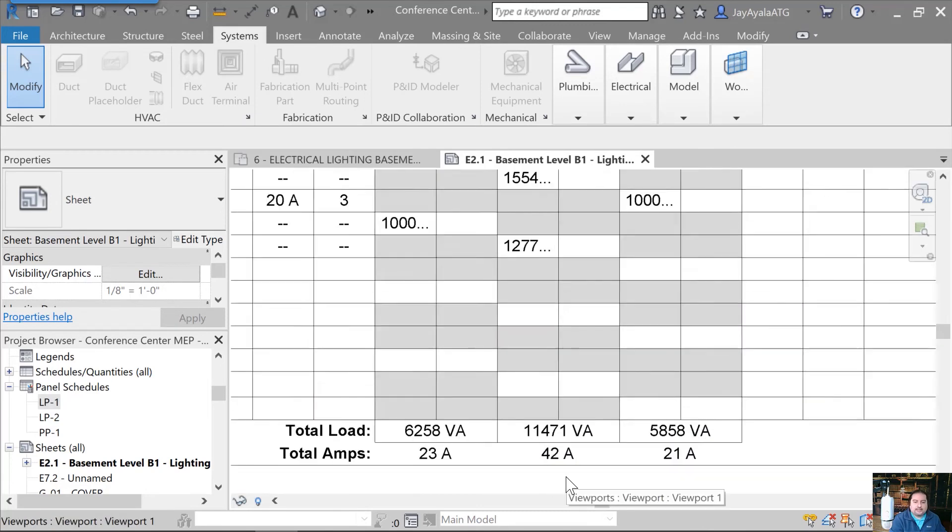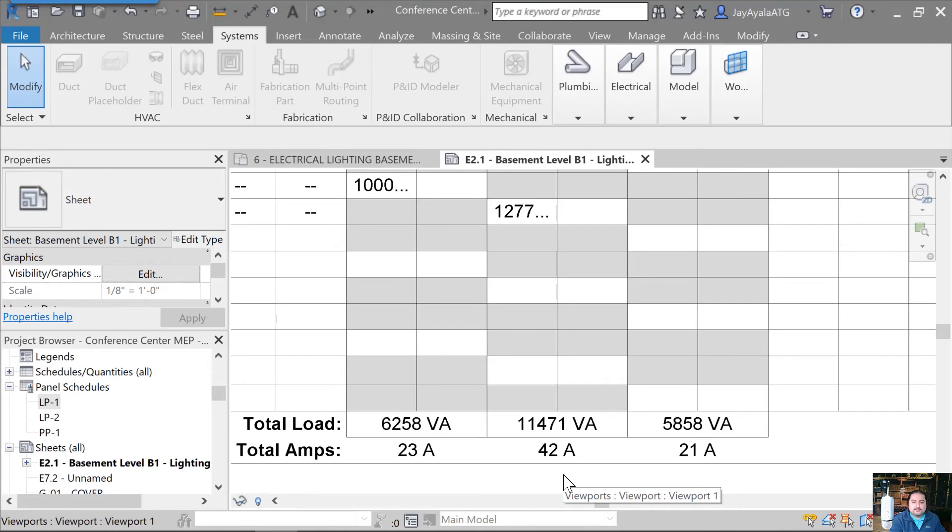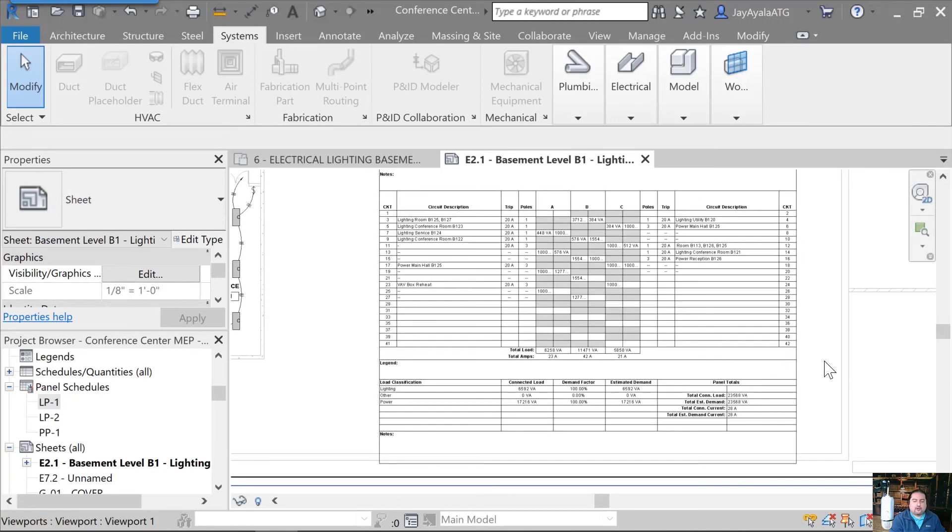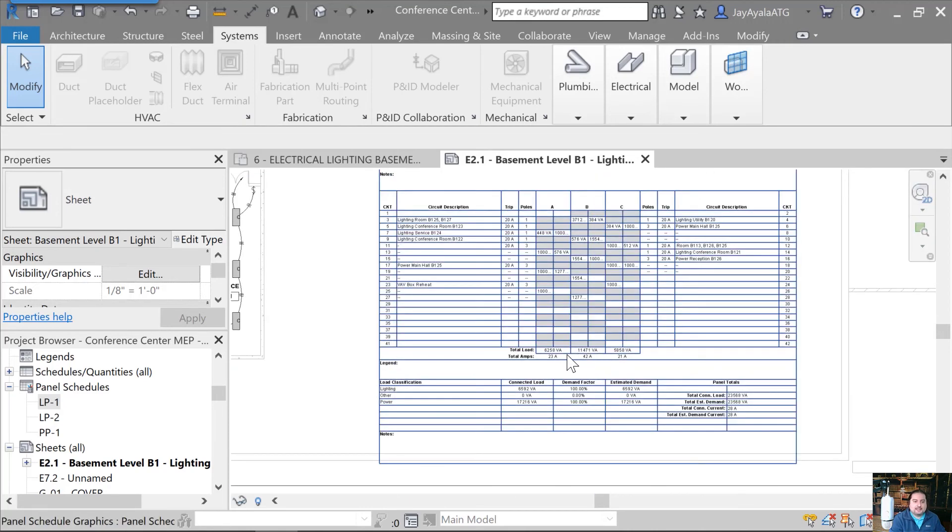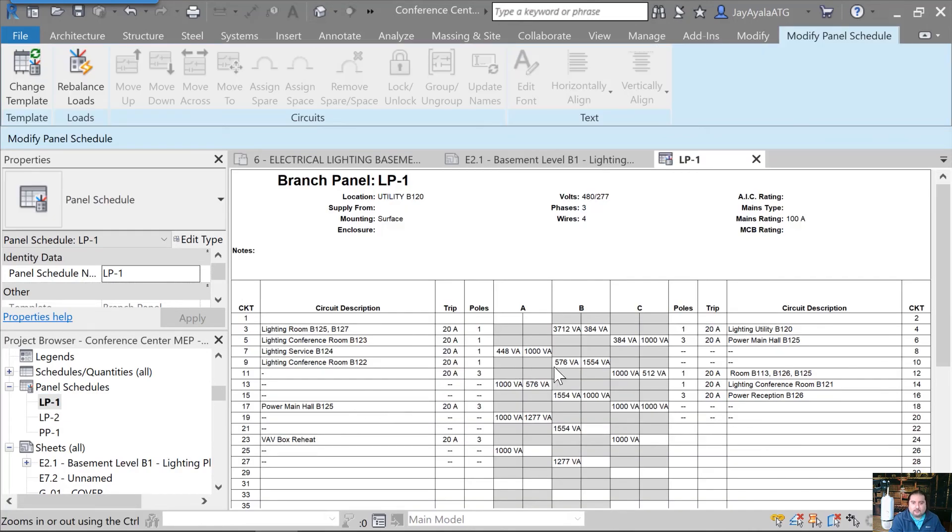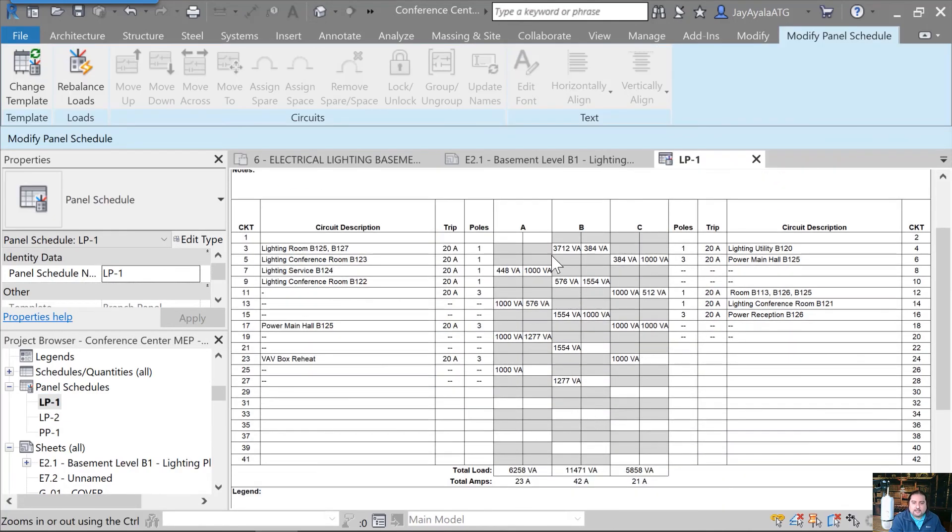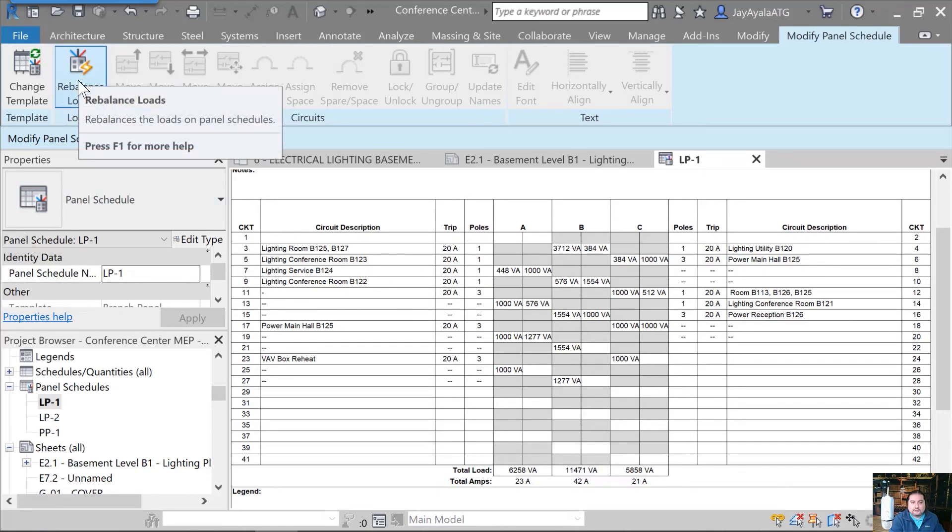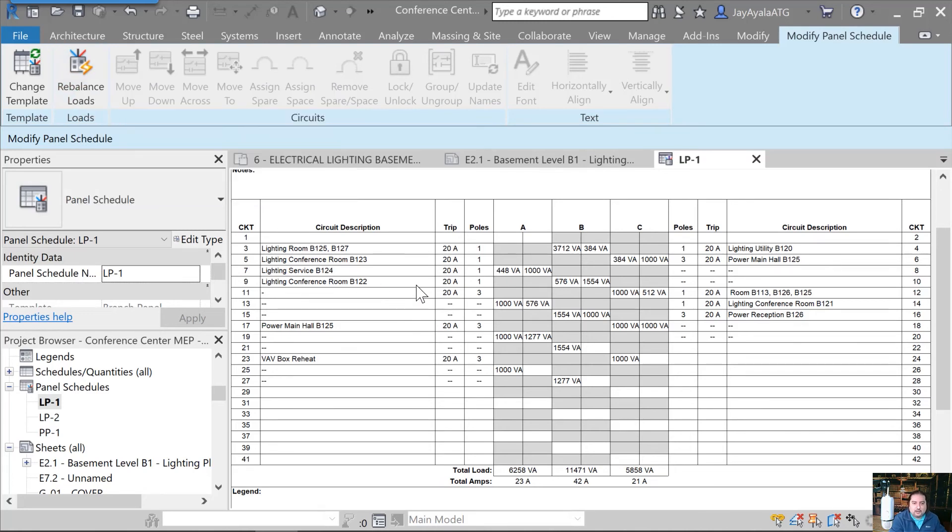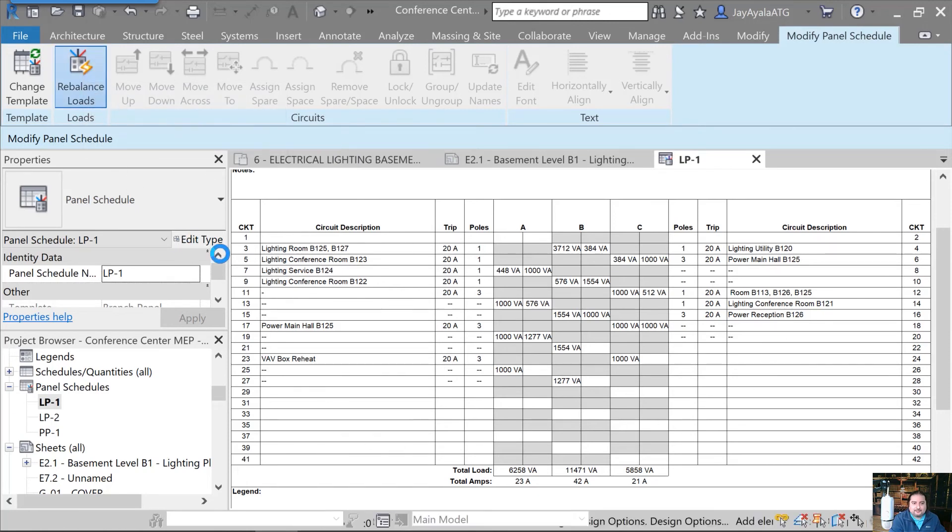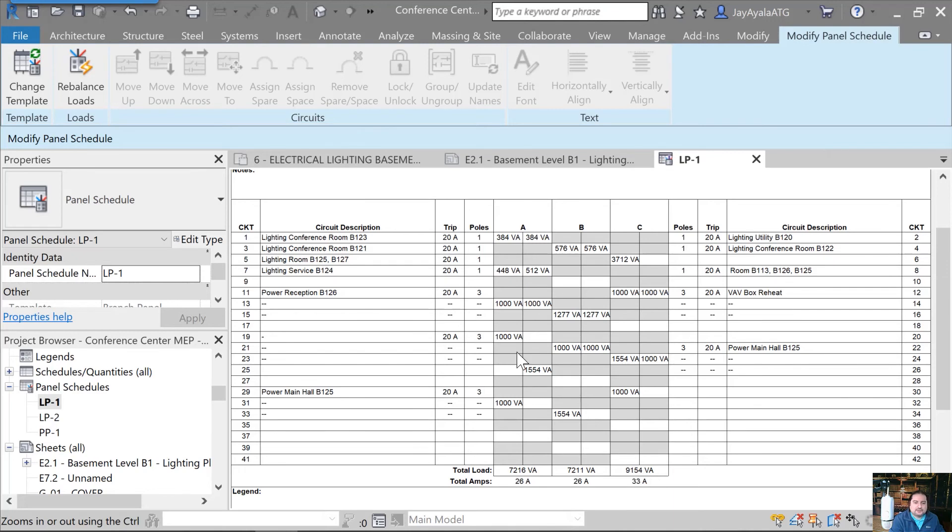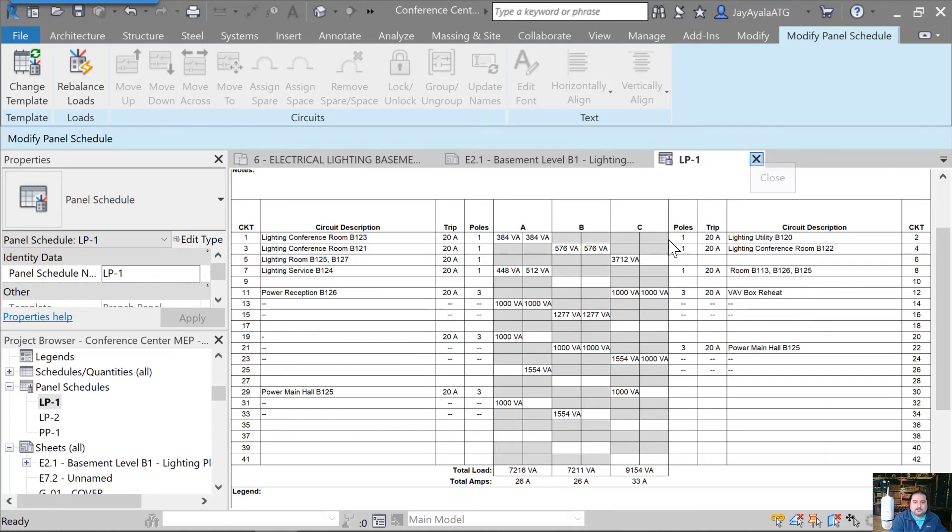Now, one quick thing that you might notice in phase A, B and C is that this is not balanced very well. So that might cause a little bit of a problem across those three phases. So I want to let you know that if we go open LP-1, here's the panel. And we can see across phase A, B and C, these are not balanced very well. And I can simply look at this. So in Excel, you can do this, but it takes quite a while to jumble all these up. Now watch what happens to the circuits when I rebalance this. And what you're going to see is that they get balanced and that they switch different locations and look at the values all the way across. That's in much better balance now. So some of these circuits jumped up, some of them jumped down, some of them even switched over across to the other side of the panel and vice versa. So that was done automatically for us.